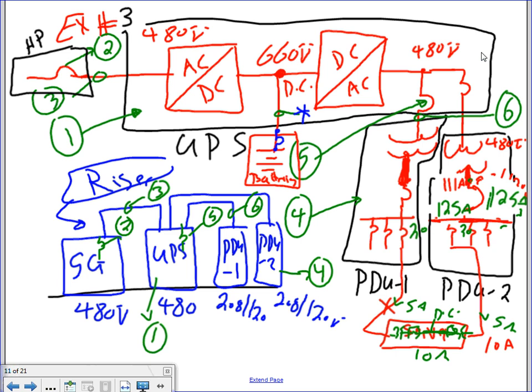So can you guys see that on the primary side it is typically 480, secondary side is 208. There's a main circuit breaker inside the box. Can you guys see these mains? And there are 20 amp circuit breakers here. It's a panel, and you bring a branch circuit to feed that server right here, from both sides. And when we go to Allianz, we will open the raised floor, they call it a raised floor, and you will stick your head down there, and you will see the feeders coming to a receptacle and plugging into these servers and feeding up.